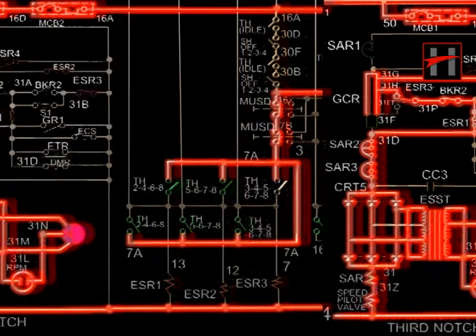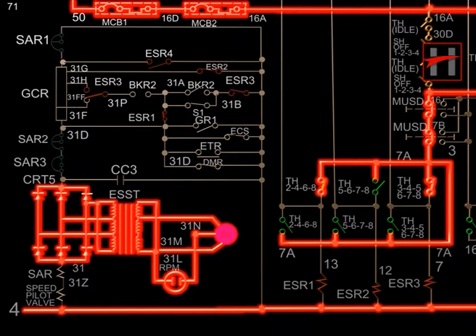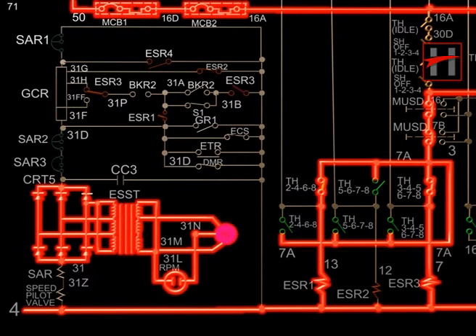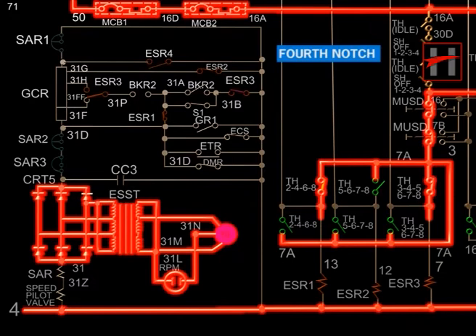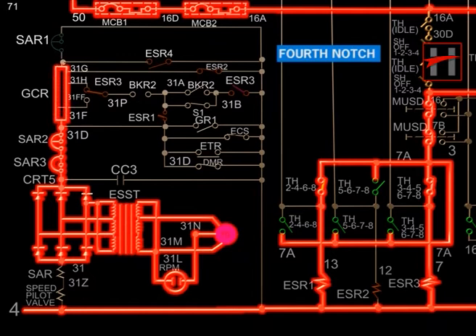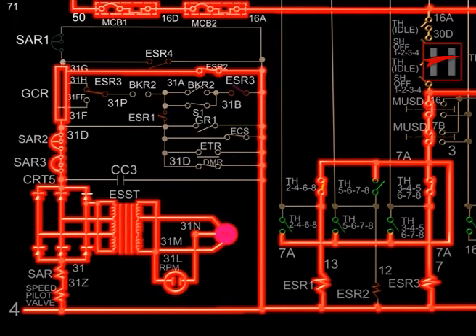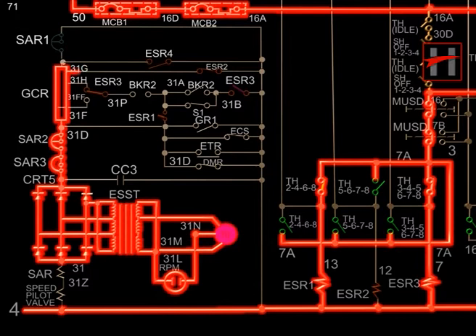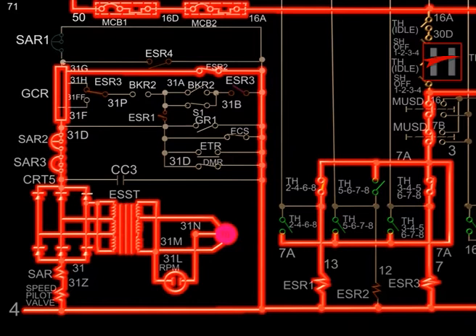In the fourth notch position, ESR-1 and ESR-3 get energized. The normally closed interlock of ESR-1 opens due to energization of ESR-1. The interlock of ESR-3 changes position from 31F to 31FF. The rectified output of the tacho generator flows through CRT-5, SAR-3, SAR-2, GCR, cable number 31H, interlock of ESR-2, and completes its path with cable number 4, speed coil of pilot valve, cable number 31Z, SAR coil, and cable number 31.